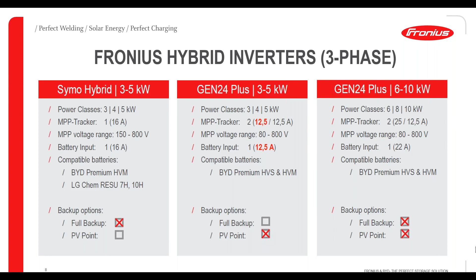Then the new models we are going to launch in a few weeks have 2 MPPTs, 3 to 5 kilowatts again with 2 MPPTs. The first one, 12.5 amps, one single string, and the second MPPT again 12.5 amps. And here we have PV point on board, but no full backup.